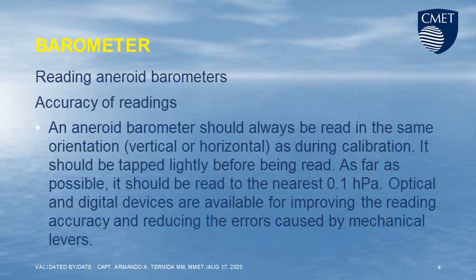Barometer reading — aneroid barometers. Accuracy of readings: an aneroid barometer should always be read in the same orientation, vertical or horizontal, as during calibration. It should be tapped lightly before being read. As far as possible, it should be read to the nearest 0.1 hPa. Optical and digital devices are available for improving reading accuracy and reducing errors caused by mechanical levers.